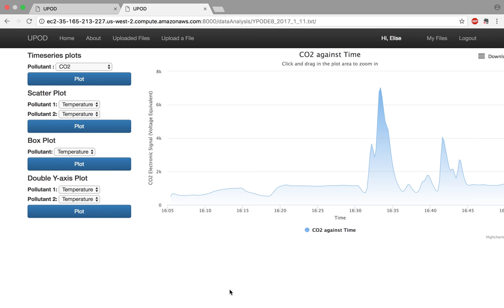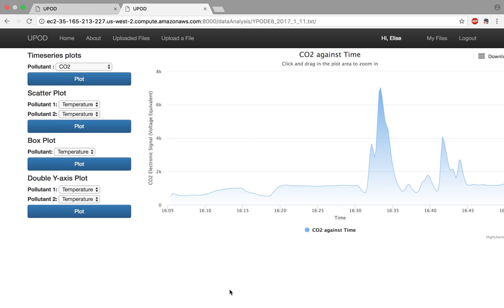This is the raw signal you will see from your pod before any calibration is applied to convert voltage into a concentration unit of parts per million or parts per billion. So when you look at this first plot and see electrical signal, electronic signal voltage equivalent, these are not concentration units. This is strictly just what the carbon dioxide sensor initially reads during your testing.